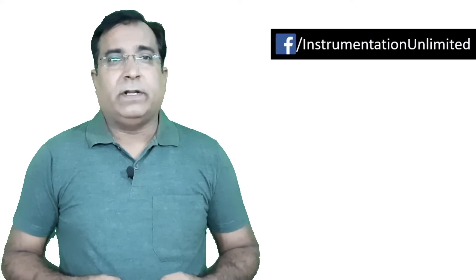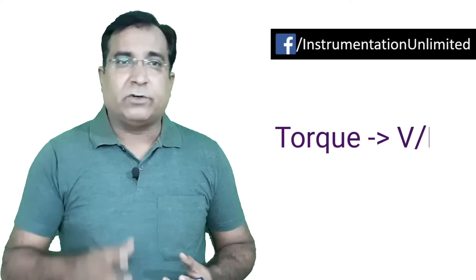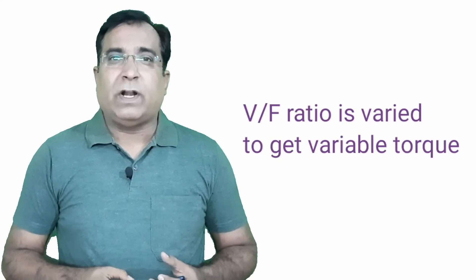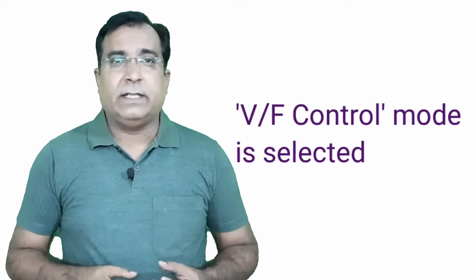Now how to program VFD for a variable torque? Because the torque of a motor is proportional to the ratio of voltage and frequency, so we have to make it vary as per your requirement. So while programming, V/F control is selected and there is an option for V by F pattern selection.